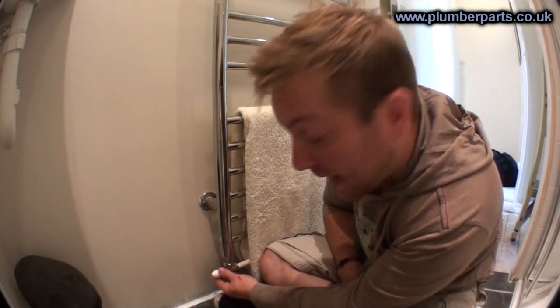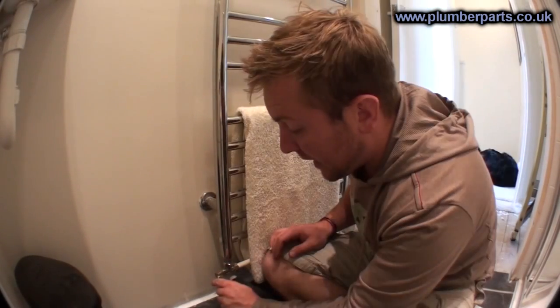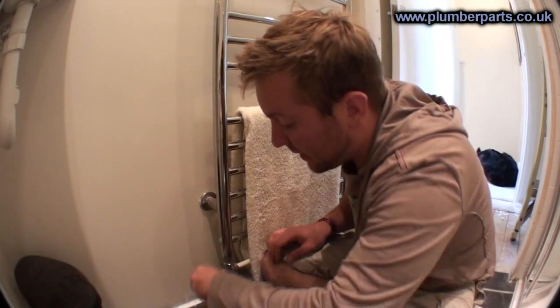So here we are with our first upstairs radiator. There's four on this system upstairs, and do the same thing to each one. Here's the lock shield end, not the TRV end. Pop the lock shield cap off, and close it by turning it clockwise.